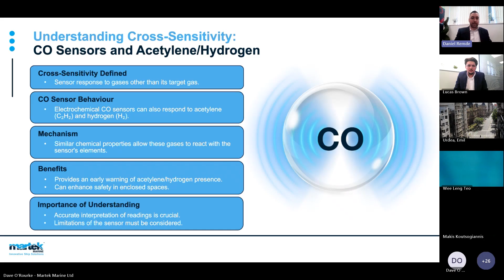There can be a benefit to this. It can provide early warning for other gases that aren't specifically targeted, which the gas detector wouldn't otherwise be capable of detecting, and therefore it can enhance safety in enclosed spaces. But understanding cross-sensitivity is crucial - you need to make an accurate interpretation of the readings, combining knowledge of what gases might be present with the capabilities of the equipment itself. It's important to note that every gas detector and every sensor is different, so you always need to check cross-sensitivity with the sensor's manufacturer and have solid data on the specific sensor you're using. But it can provide benefits if used correctly.